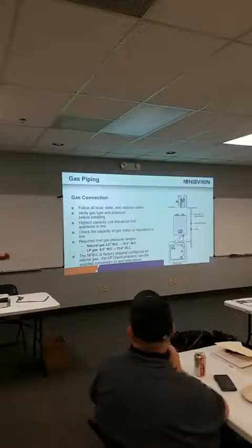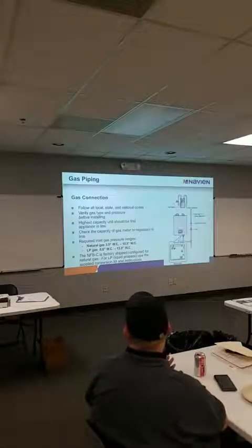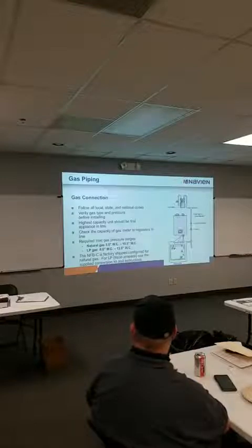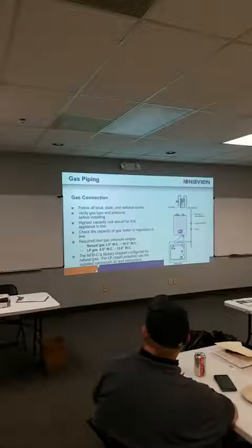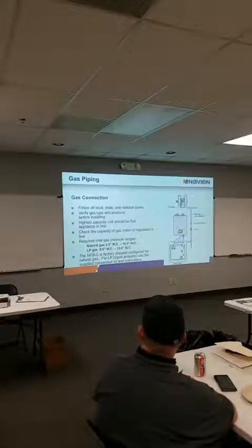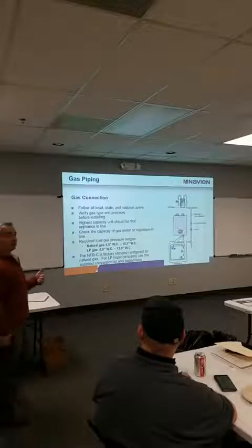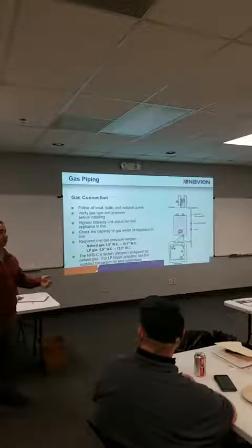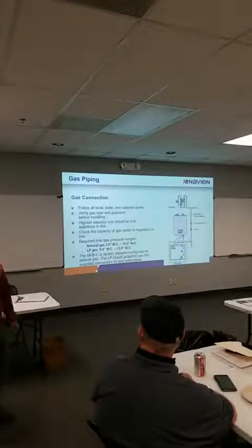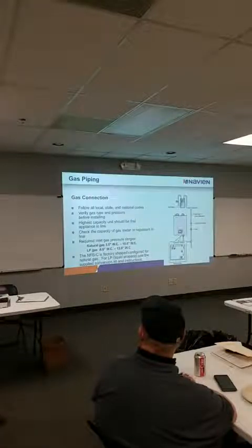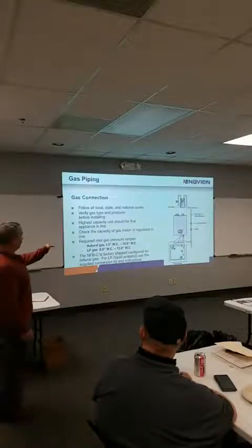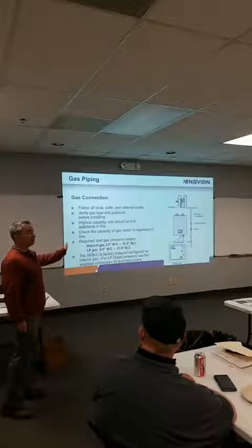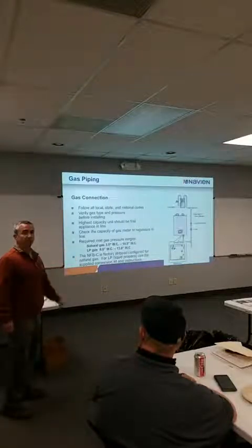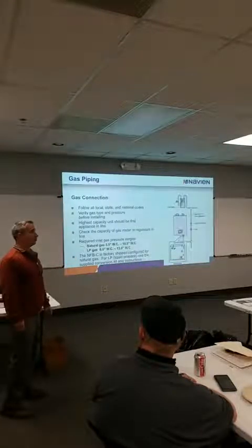All of our equipment on natural gas falls between 3.5 and 10.5. Same on LP. We use the 3-inch water column drop chart, and we allow up to 3 inches of drop before we want to start looking at piping issues. So you can have this system set up where you're only getting 3.5 inches of water column on natural gas, and we'll allow up to a 3-inch drop, and this thing will run full BTUs.